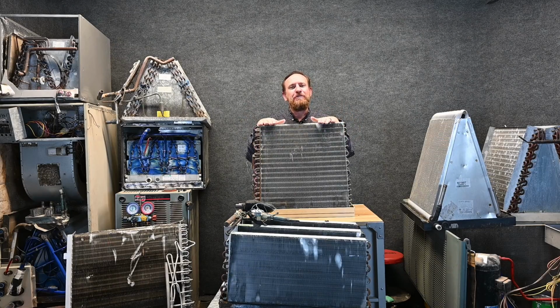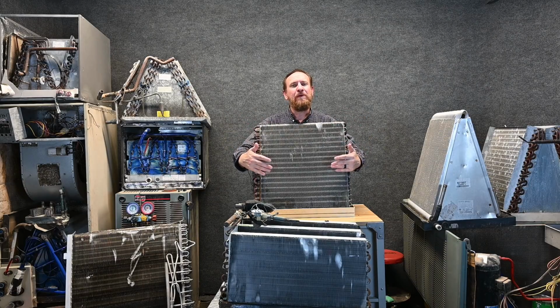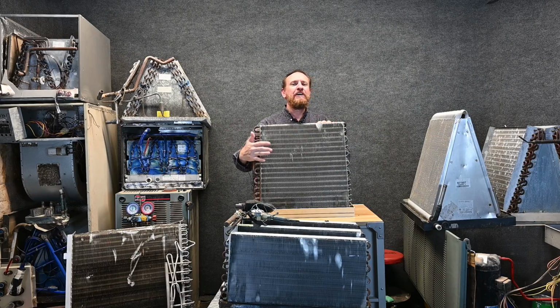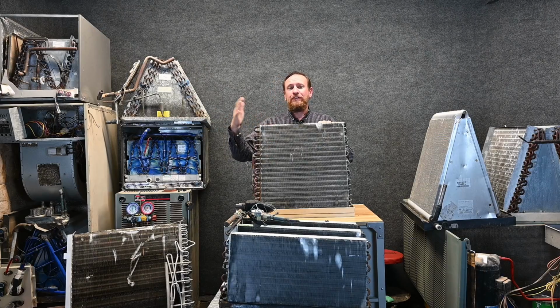And airflow is your number one issue that's overlooked in HVAC. How much air we're getting across this evaporator coil is essential. Remember, we're taking the heat out of the air, and the heat from the air is making the refrigerant boil. So they are connected together. If we don't have enough airflow, we're not going to be able to diagnose the refrigeration system properly at all. If we don't have enough air to boil the refrigerant into a vapor, superheat and subcooling doesn't matter, pressures don't matter, everything's out the window because we need to get airflow first.